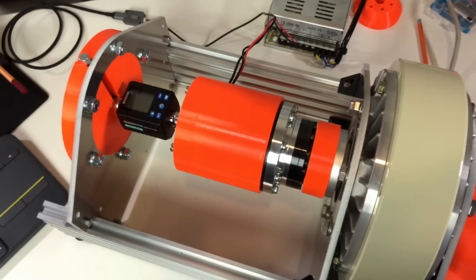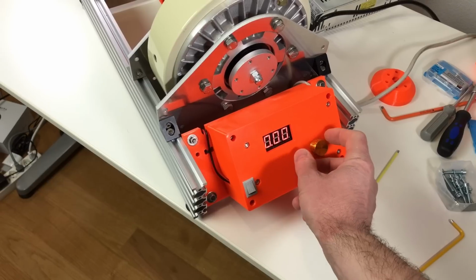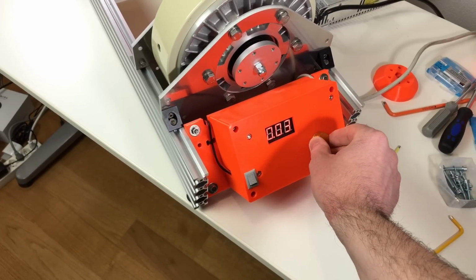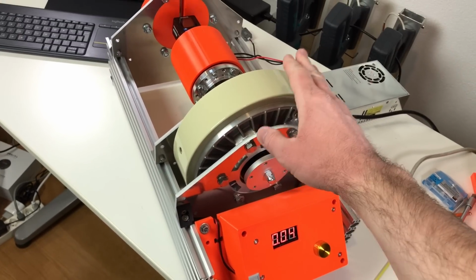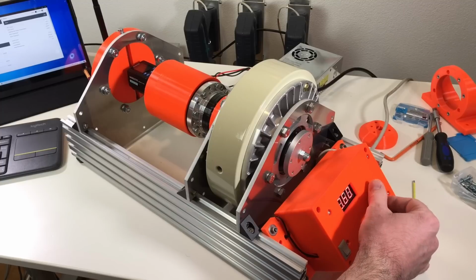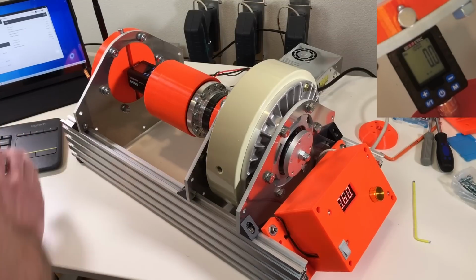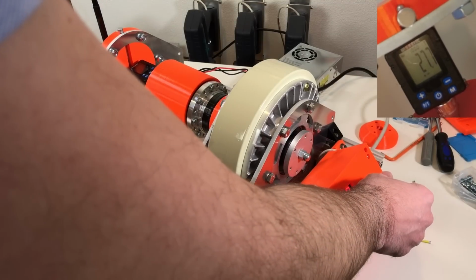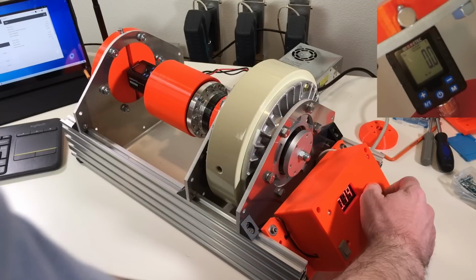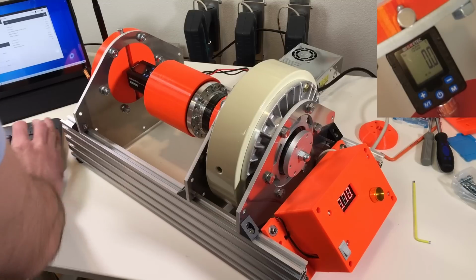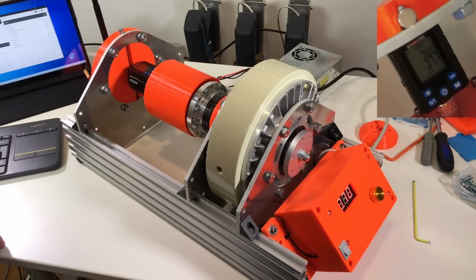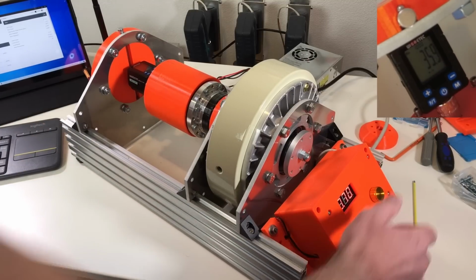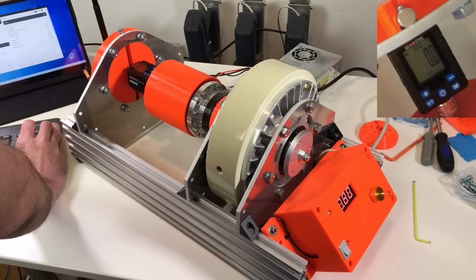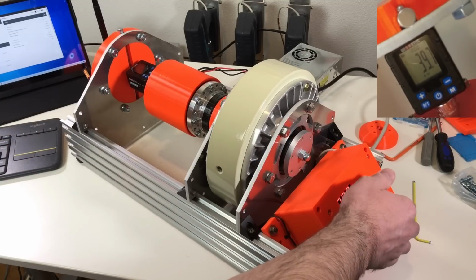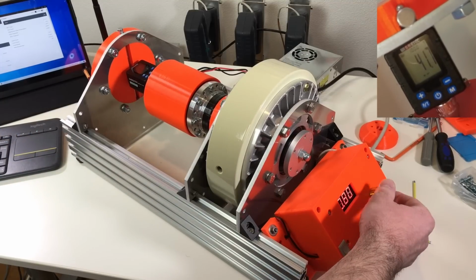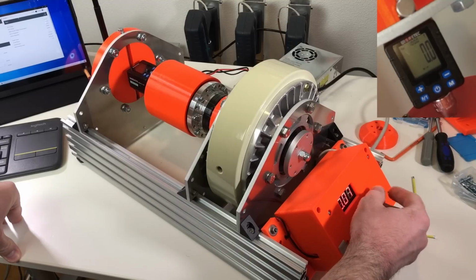The actuator is installed and we're ready for the test. Here I can change the force with which the powder electromagnetic brake is going to brake. So 0.6, go. 27 Newton meters. Now let's go to the 0.7, go. 34 Newton meters, 36 Newton meters. 0.8, go. 39 Newton meters, 40 Newton meters. Now 0.9, go.